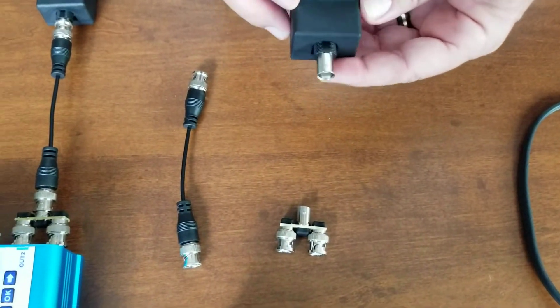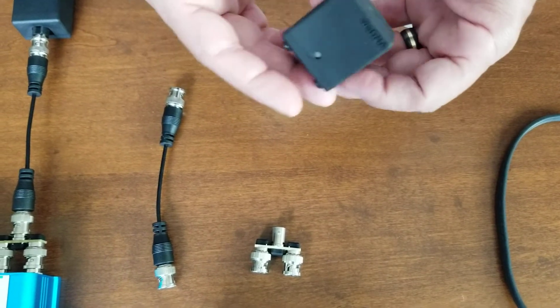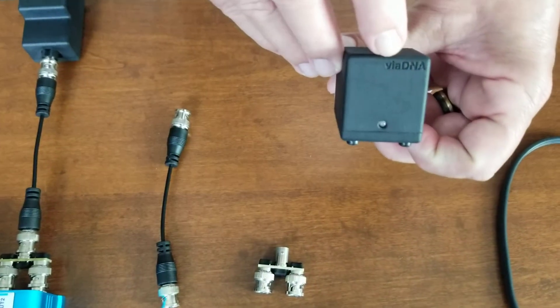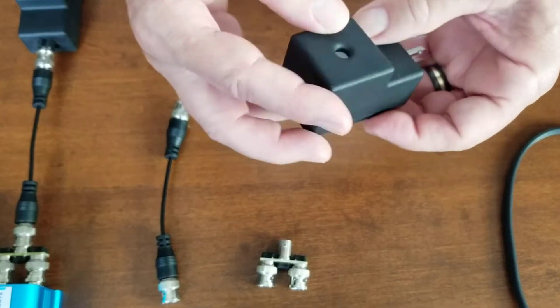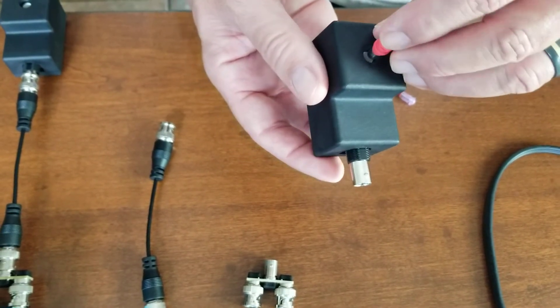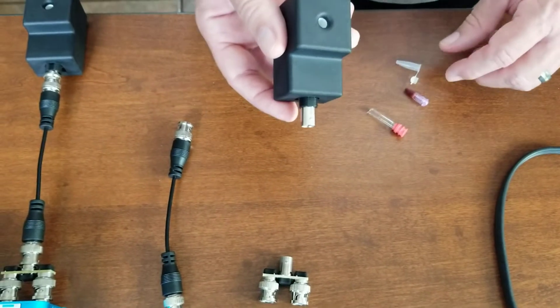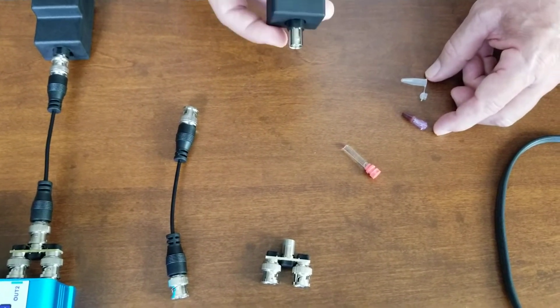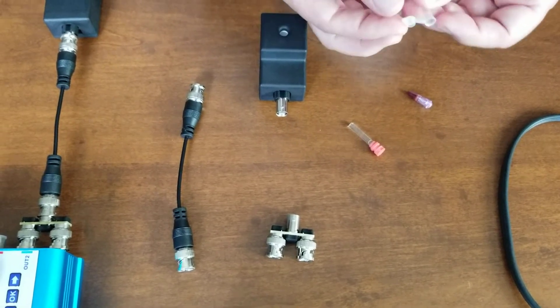Same story with the remote. It's got a BNC connector, a female. And this is our newest remote. You'll know because it has VIA DNA engraved on one of the sides. And this remote is capable of taking not only the standard five milliliter glass vial, but also a new vial that we're going to be shipping later this year, 2020, which is completely made out of plastic polycarbonate and comes with its own cap already attached.